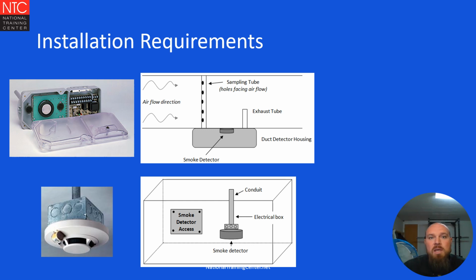If you're utilizing an outside duct detector, it'll be mounted to the outside of the ductwork itself. Your sampling tube will be in the ductwork itself. You want to make sure that the slots of the tube are in the same flow of the air itself so that it can actually sample the air as it flows through. Your in-duct smoke detectors are mounted to the inside of the duct housing and of the ductwork itself. They can be mounted directly to the wall. Oftentimes, though, they will be suspended down from the ductwork itself.